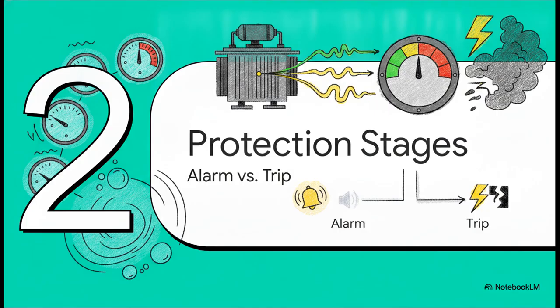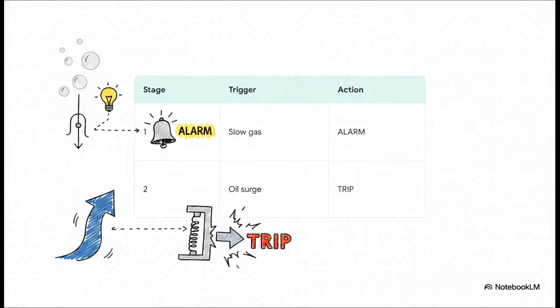Section 2. Two stages of protection. Alarm versus trip. Because this relay reads physical conditions, it doesn't just have a simple on-off reaction. It actually scales its response based on how bad the fault inside the tank really is. As you can see, we typically have 2 stages here. Stage 1 is triggered by that slow gas accumulation we were just talking about. The float drops, and you get an alarm.